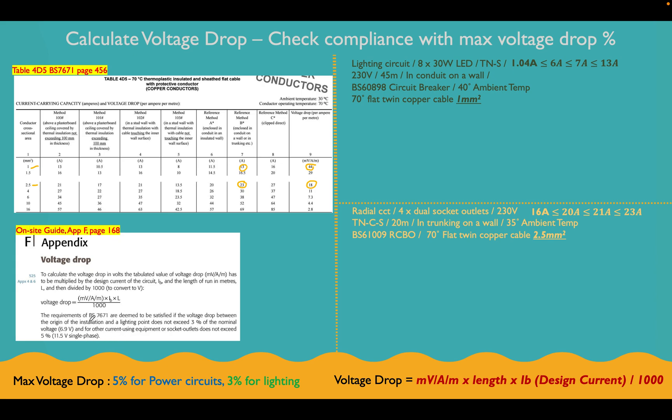Let's read here, just in case we forget this. The requirements of 7671 are deemed to be satisfied if voltage drop between the origin of the installation and a lighting point does not exceed 3% of the nominal voltage. So basically, from the start to the end of our circuit, we need the voltage drop to not exceed 3%.